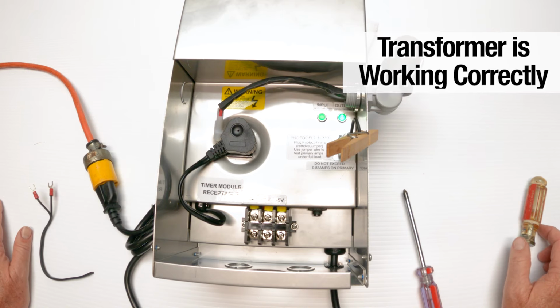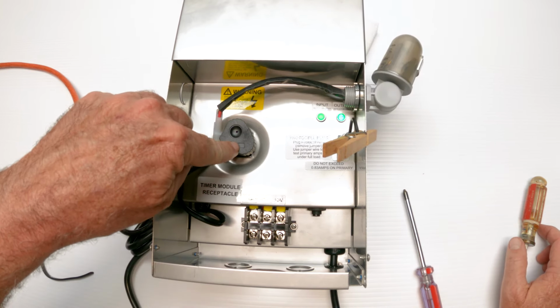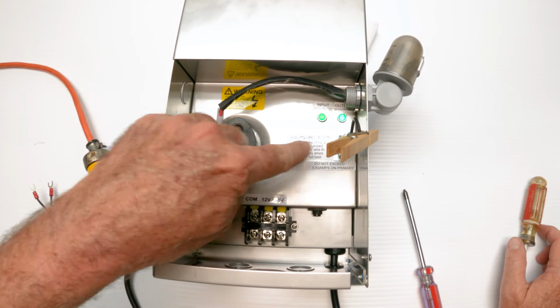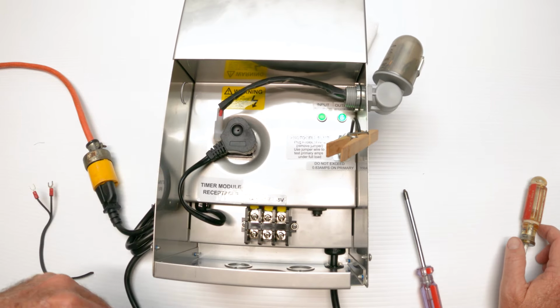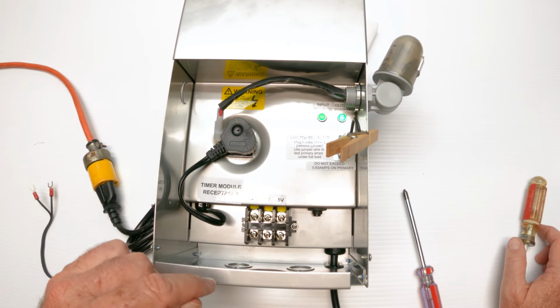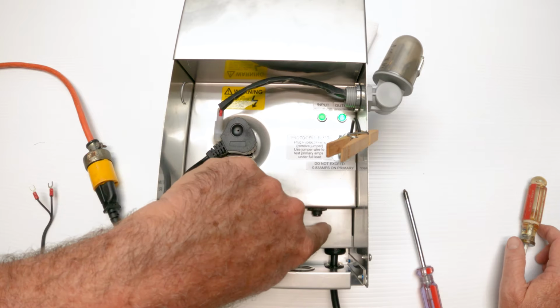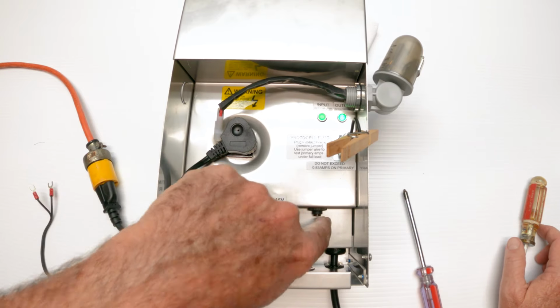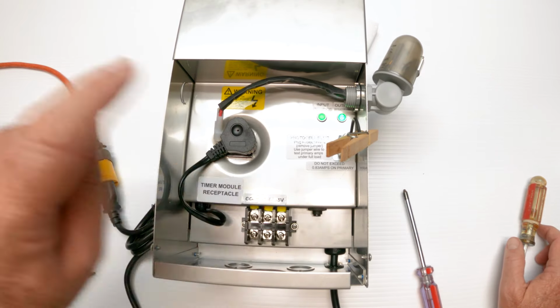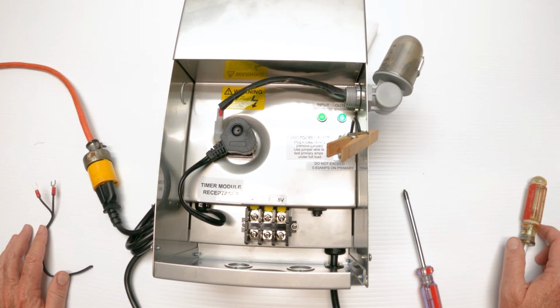So the problem was possibly the timer, possibly the photocell, or possibly a short out in the field. If there's a short in the field, most likely this little circuit breaker would have popped and you'd have to push it in. It's a great indicator if there's a problem in the field.